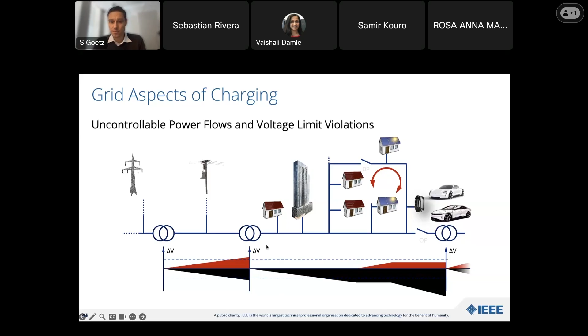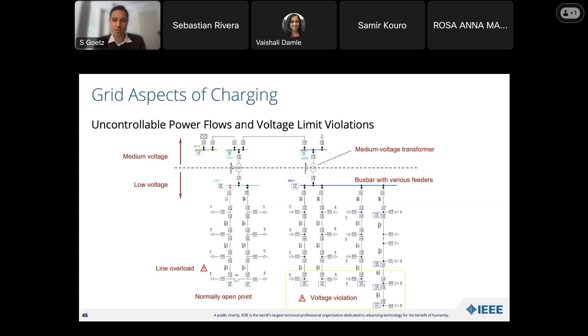And here you see a typical situation, what can happen here, right? Particularly when you have, for example, at the end of a long feeder, here's medium voltage, low voltage, a long feeder, at the end, for example, some new buildings attached, they get solar systems, they want to have chargers and so on, and suddenly run into voltage violations. You might also overload some lines because, right, solar system here and some charger here, and suddenly you have lots of load on one line.